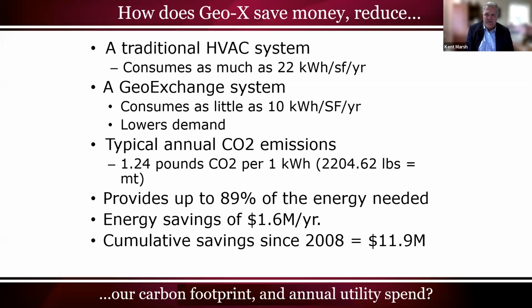Probably the last slide I'll be able to touch on: HVAC systems traditionally consume about 22 kilowatt hours per square foot of connected load per year. Our Geo system consumes less than half of that, at 10 kilowatt hours per square foot. That equates to savings of about $1.6 million per year. With the $20 million we've invested, we've reduced our payback from the traditional 20-plus years for a Geo system down to our current payback of about 12 years.